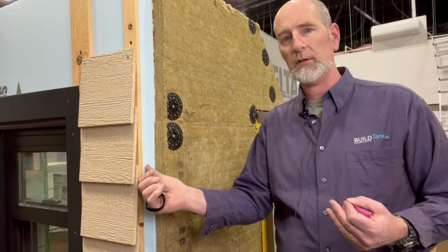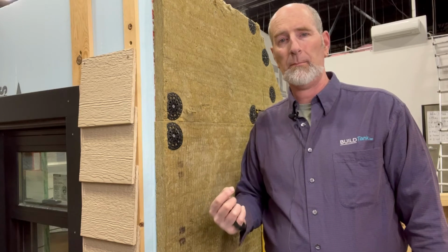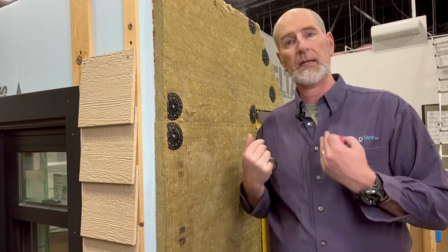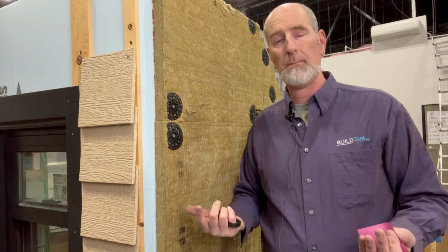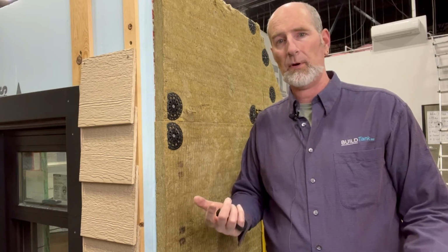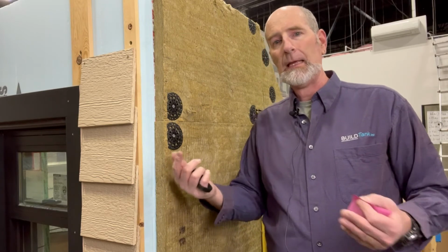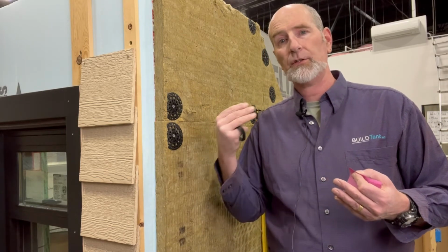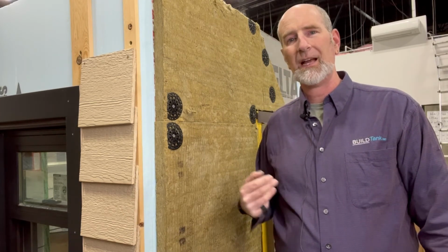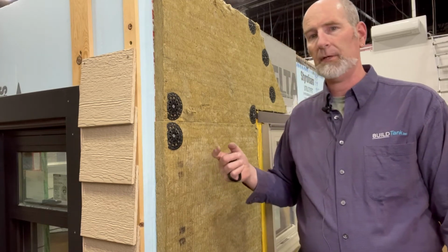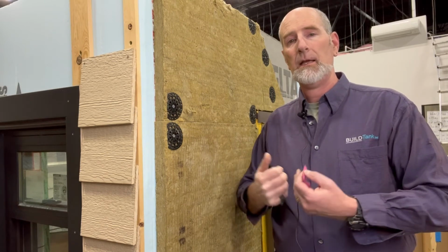Now, a lot of the foam boards, especially the skin foam boards that have that plastic film on them, have really limited permeability. So I'm going to have to ensure that my drying potential is all to the inside. So I'm going to have to choose a Class 3 vapor retarder or one of these smart membranes, like CertainTeed's membrane, for example. Siga and others make some as well, that can stop moisture diffusion in one direction but allow that diffusion back out of the assembly in the other direction. Kind of like a Gore-Tex jacket has the ability to do that. So I want to ensure that I have drying potential at least in one direction, ideally in both directions.